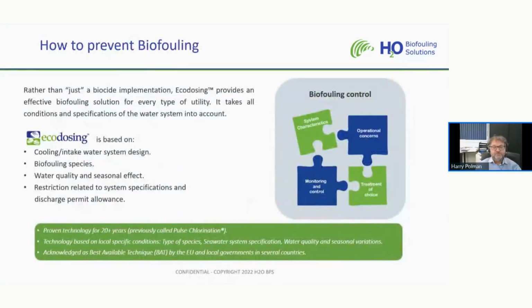How do you prevent biofouling? Instead of just dosing a biocide, we combine Ecodosing with system characteristics, operational concerns, and monitoring and control to make a treatment choice. The design of Ecodosing is based on local specific conditions — the local biofouling species, water quality, seasonal effects, and restrictions related to discharge permit allowance.